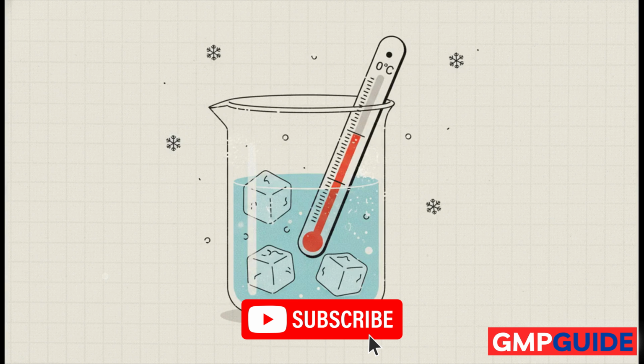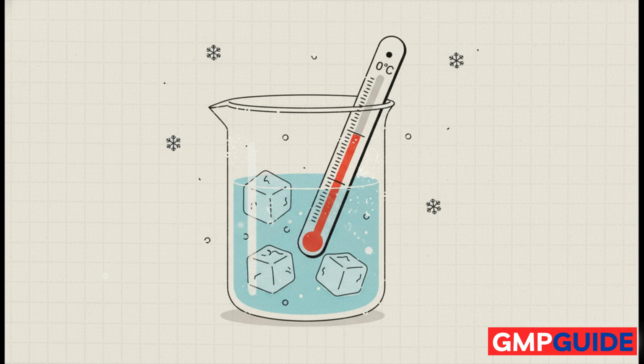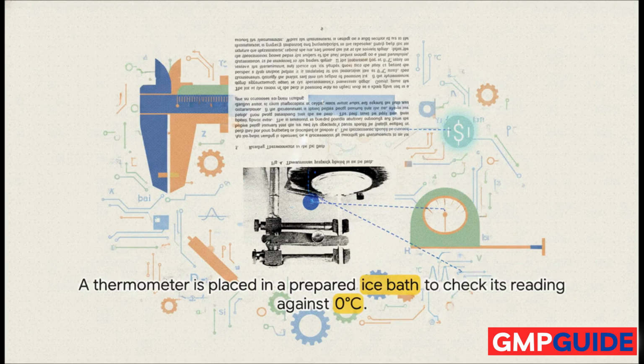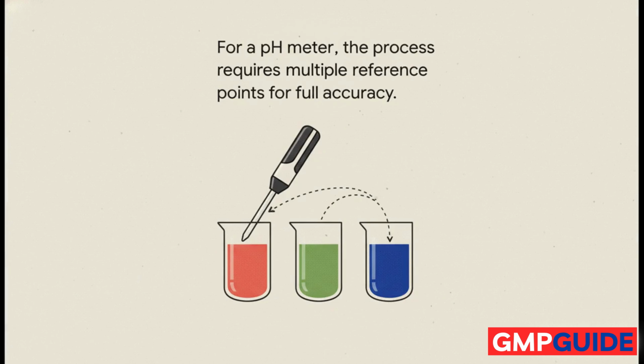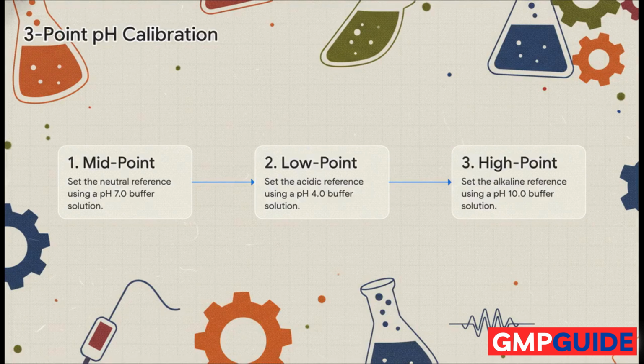First up, a thermometer. A common check uses a simple, natural standard, the exact freezing point of water. A technician just puts the thermometer in a prepared ice bath. The reading has to be exactly 0 degrees Celsius. But for more complex tools like a pH meter, you need multiple points of reference to be accurate. A 3-point calibration uses standard solutions, acidic, neutral, and alkaline, to guarantee accuracy across the full range.